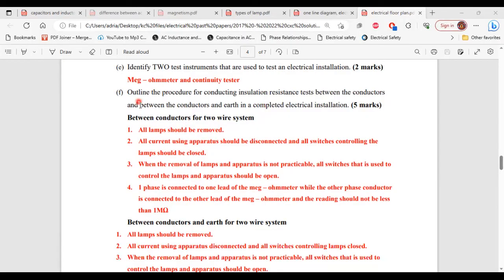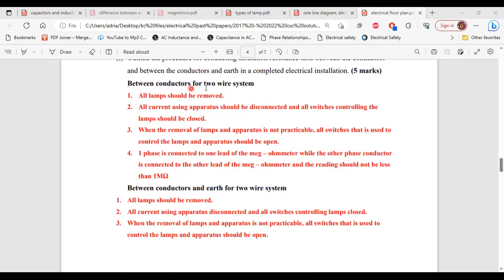Part F: insulation resistance test procedure — between conductors for a two-wire system. 1 — all lamps should be removed. 2 — all current-using apparatus should be disconnected and all switches controlling the lamps should be closed. 3 — when removal of lamps and apparatus is not practicable, all switches used to control them should be open. 4 — one phase conductor is connected to one lead of the megohm meter while the other phase conductor is connected to the other lead; the reading should not be less than one megohm.